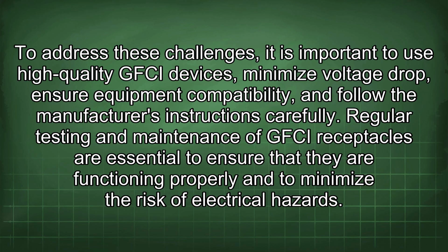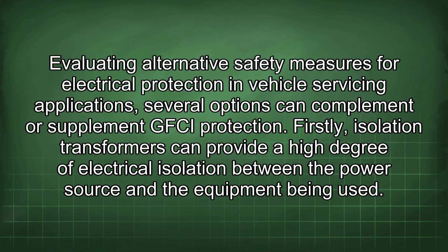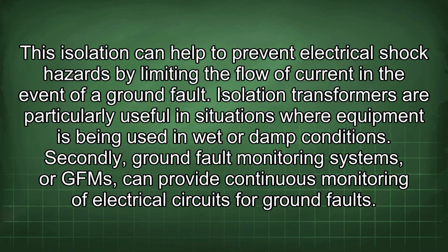risk of electrical hazards. Evaluating alternative safety measures for electrical protection in vehicle servicing applications, several options can complement or supplement GFCI protection. Firstly, isolation transformers can provide a high degree of electrical isolation between the power source and the equipment being used. This isolation can help to prevent electrical shock hazards by limiting the flow of current in the event of a ground fault. Isolation transformers are particularly useful in situations where equipment is being used in wet or damp conditions.